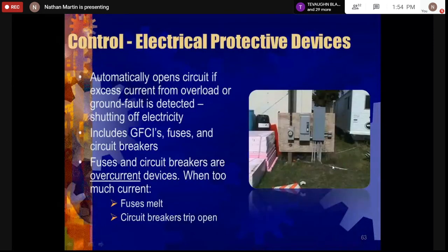Our controls will talk about this in much more detail, but another way to control these types of classified hazards is your GFCI, ground fault circuit interrupters, for persons who don't know. You may find them in your household, like in your kitchen, you'll normally find one there. If you have a plug in zone 3 in your bathroom, you might have a GFCI outlet, but our local regulation requires us to use a GFI outlet as well as a GFI breaker.